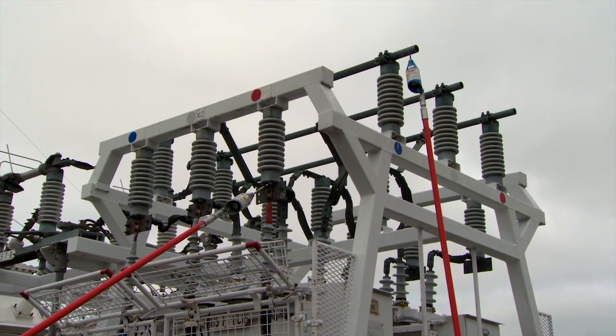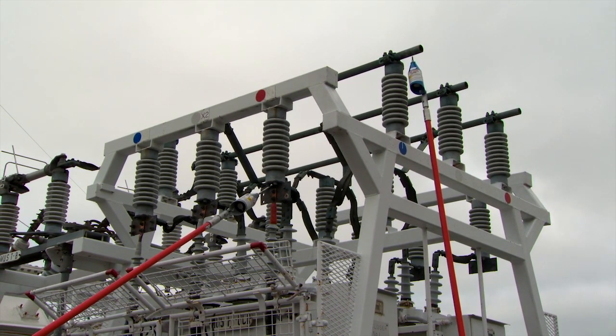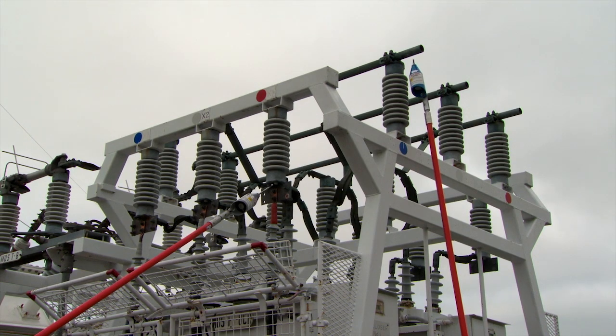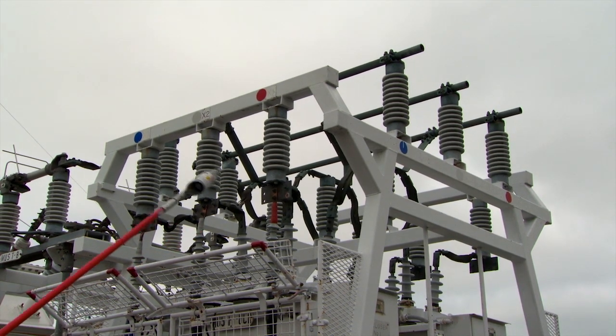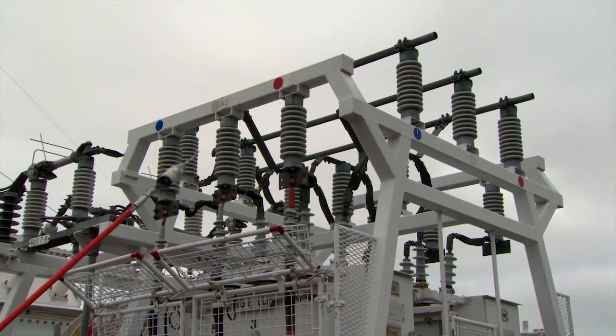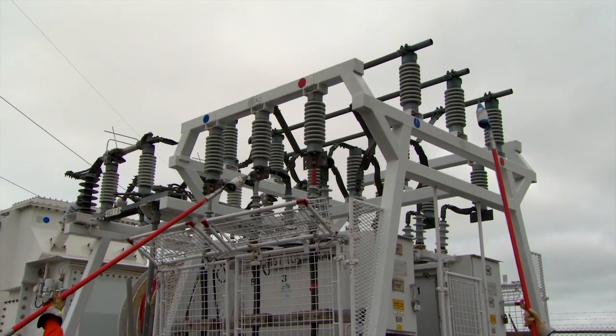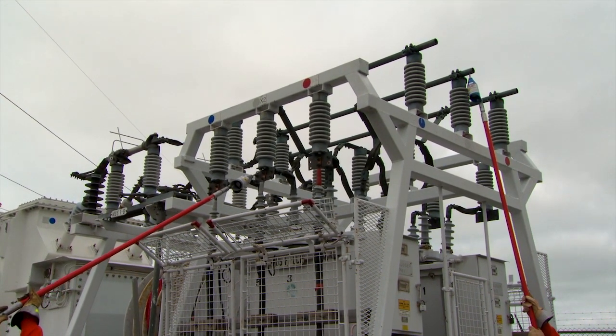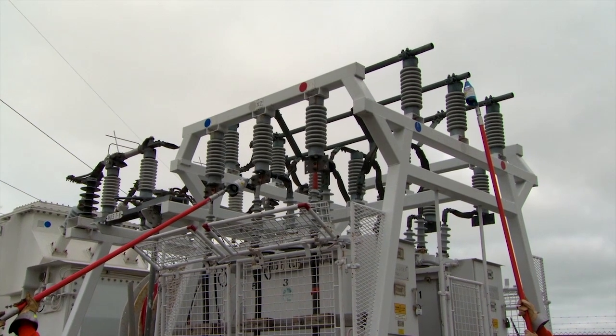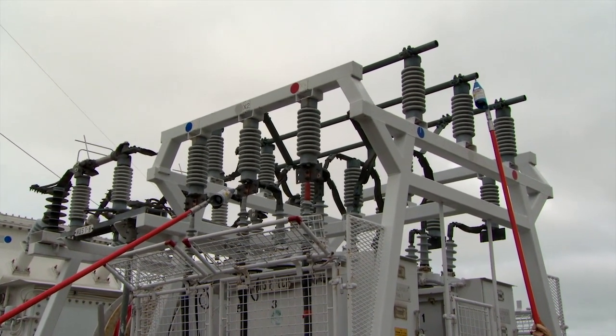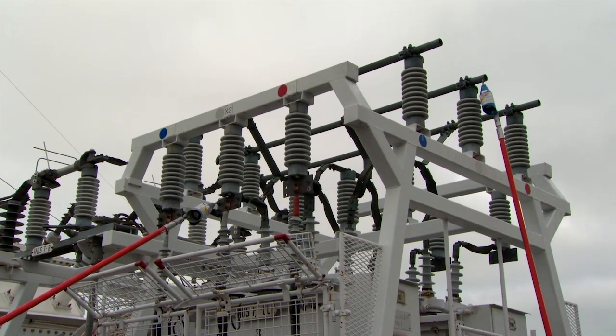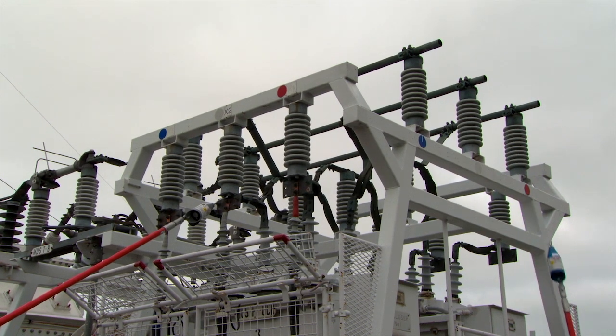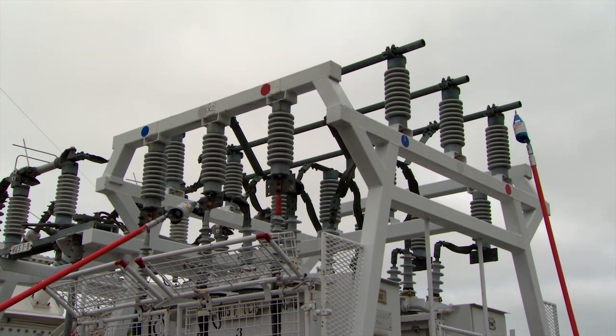They should also be tested on a known source. After the unit is confirmed functional, you can perform the required phase checks. Place the transmitter on each conductor to verify the presence of voltage. The transmitter will begin beeping with flashing lights when voltage is detected. After testing one conductor, remove the transmitter from the line and wait for all LED lights to extinguish before placing the unit on the next conductor to be tested.